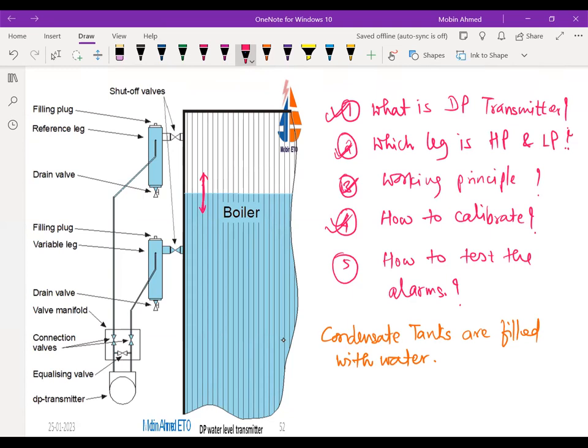Second is, just close from here these 2 points. Drain a little bit, so your steam pressure is out. And here also you can drain a little bit, so the steam pressure is out. Or if you are not able to drain, suppose because you need to go on top, and because the drain is one pipe coming from up to down below in the boiler, you might have seen. So you can drain both a little bit, so your steam pressure is not there. Open the connection from here, and put a pressure calibrator. Okay, so the pressure calibrator is there, and little by little you can increase the pressure.